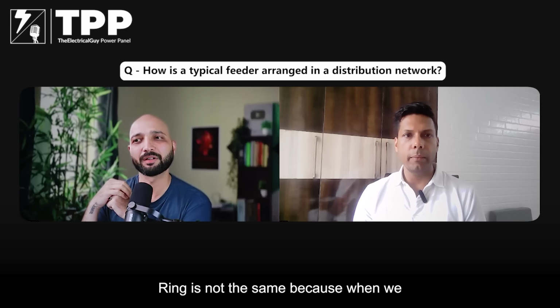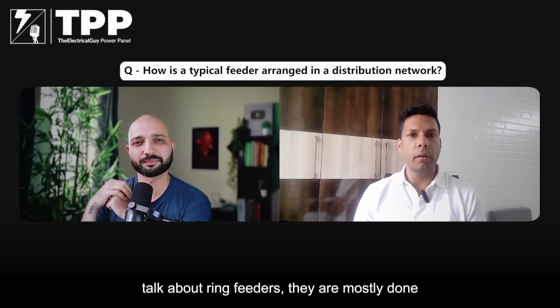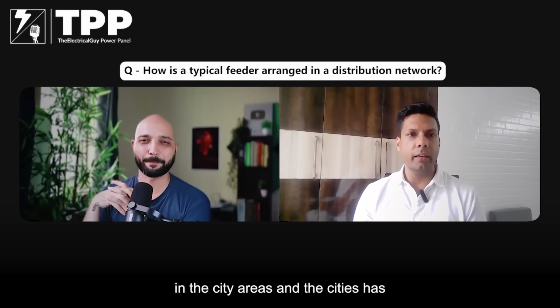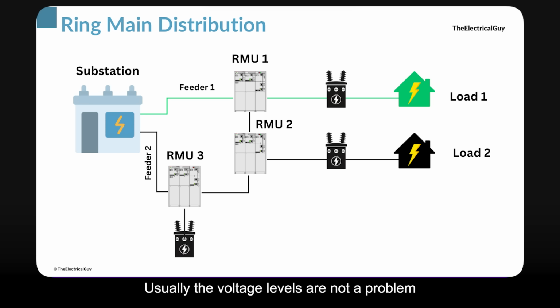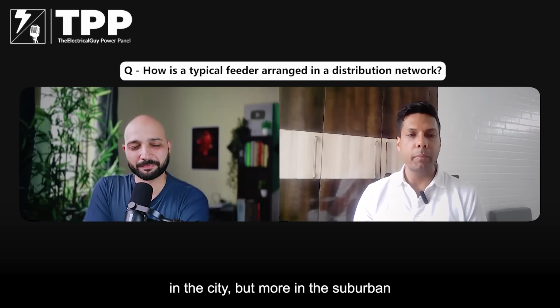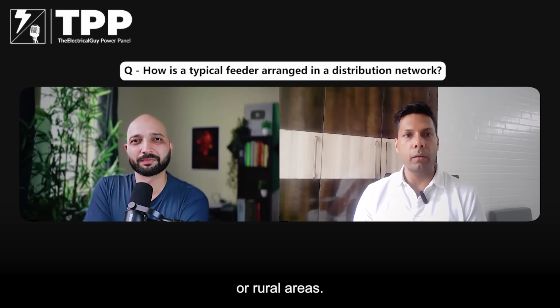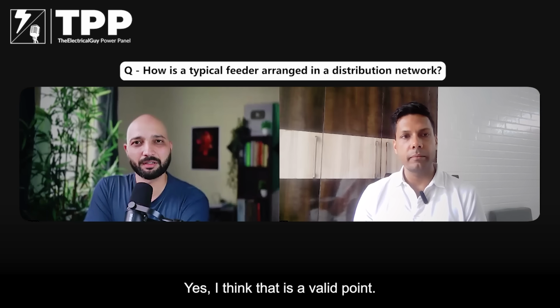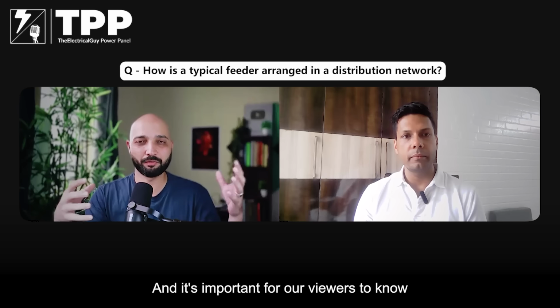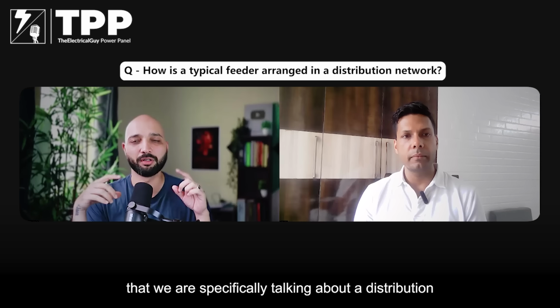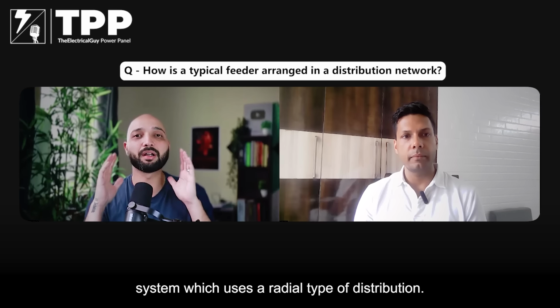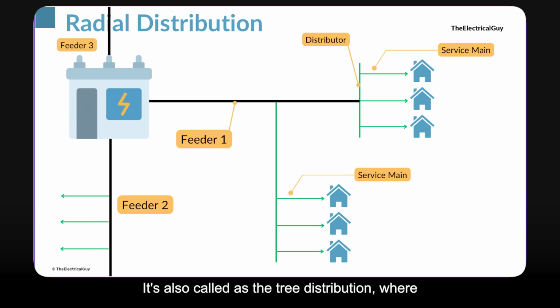Ring is not the same, because when we talk about ring feeders, they are mostly done in the city areas, and the cities have a limited geography. So usually the voltage levels are not a problem in the city, but more in the suburban or rural areas. Yes, that is a valid point, and it's important for our viewers to know that we are specifically talking about a distribution system which uses a radial type of distribution. It's also called the tree distribution, where we have one single feeder and we take a lot of branches out of it. That's how a radial feeder is generally arranged.